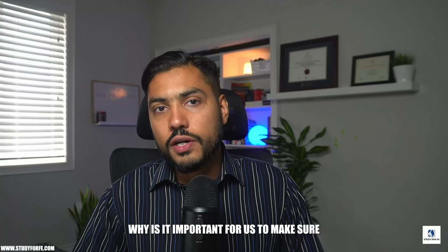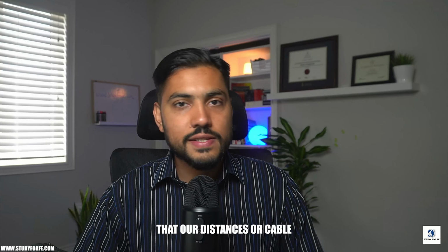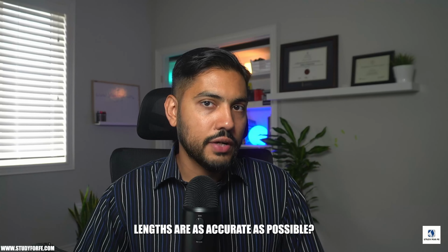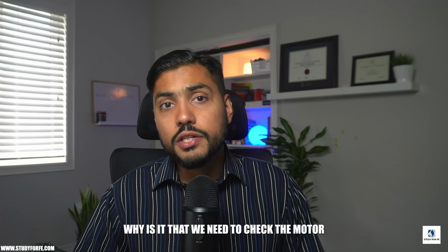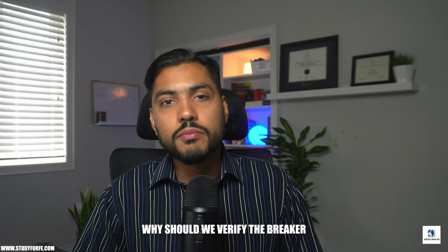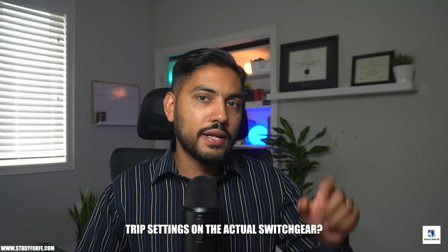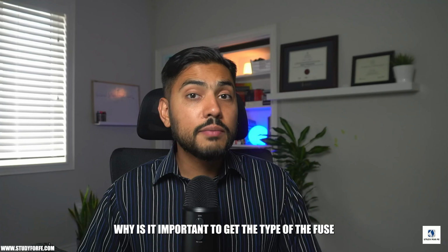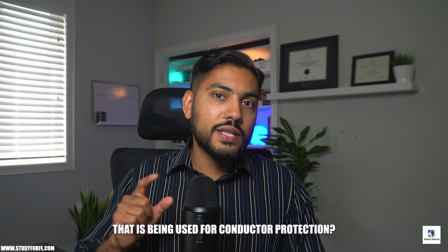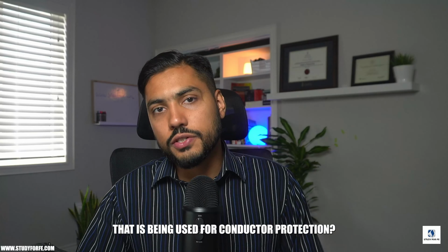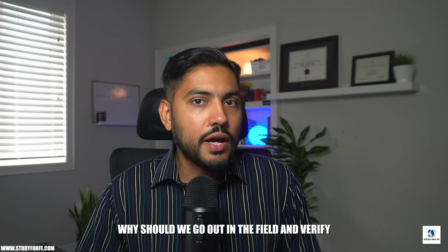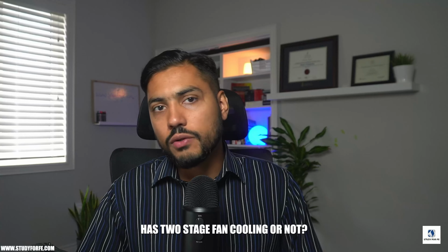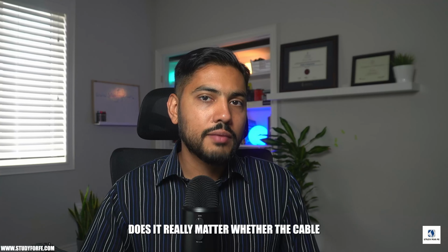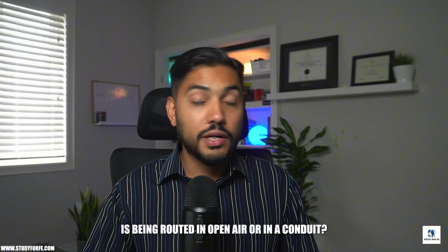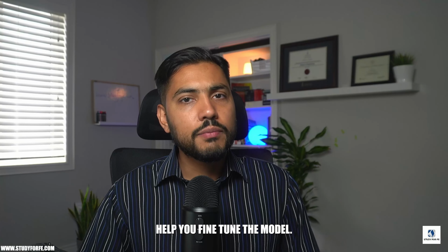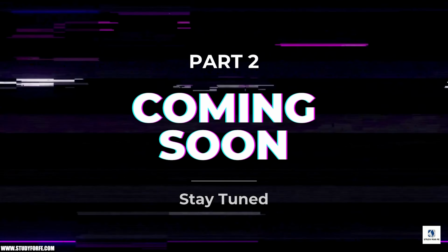Why is it important for us to make sure that our distances for cable lengths are as accurate as possible? Why do we need to check the motor nameplate data? Why should we verify the breaker trip settings on the actual switchgear? Why is it important to get the type of fuse used for conductor protection? Why should we go out in the field and verify whether the transformer has two-stage fan cooling or not? Does it really matter whether the cable is routed in open air or in a conduit? All of these questions will help you fine-tune the model.